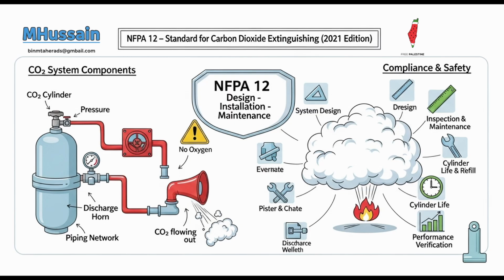And speaking of precision, it's not just any CO2 that goes into these sophisticated systems, is it? There are surprisingly strict quality standards for the extinguishing agent itself. Absolutely. Purity matters. What are they, and why does that level of purity matter? The standard specifies very precise quality requirements for the carbon dioxide used. For instance, the vapor phase must be at least 99.5% carbon dioxide. And 99.5% pure. With no detectable off-taste or odor. The water content of the liquid phase has to comply with a specific industrial standard, CGA G6.2. CGA G6.2, okay. Which is set by the Compressed Gas Association and outlines detailed purity levels for commercial carbon dioxide.